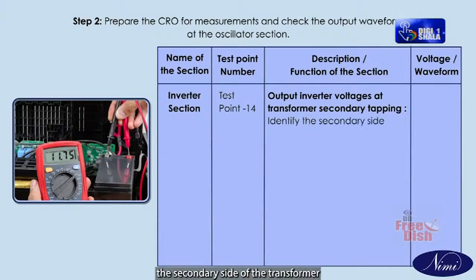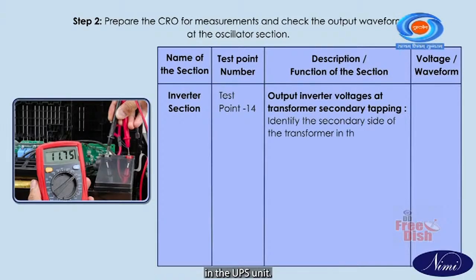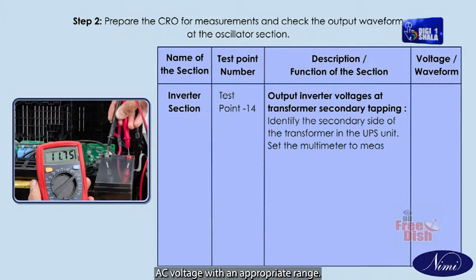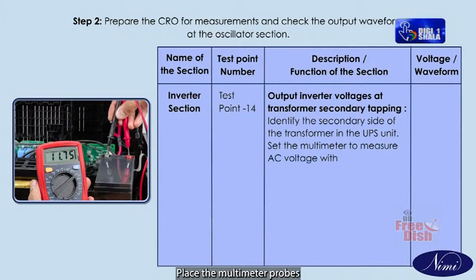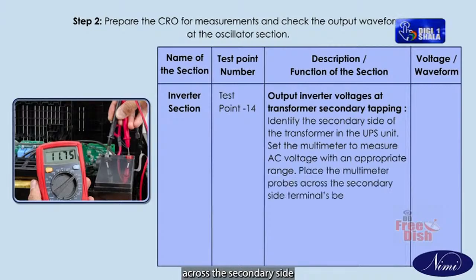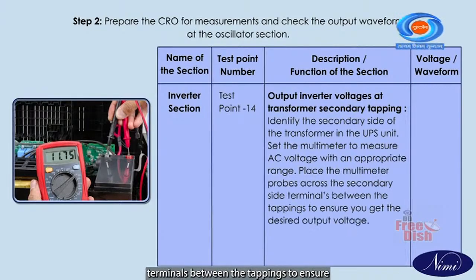Test point 14. Output inverter voltages at transformer secondary tapping. Identify the secondary side of the transformer in the UPS unit. Set the multimeter to measure AC voltage with an appropriate range. Place the multimeter probes across the secondary side terminals between the tappings to ensure you get the desired output voltage.